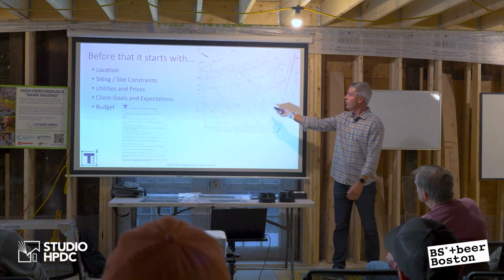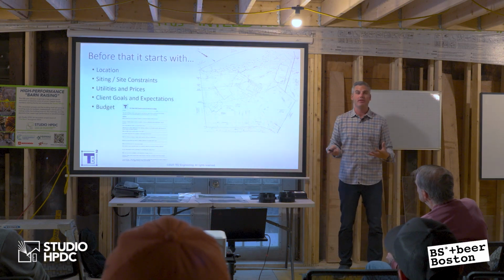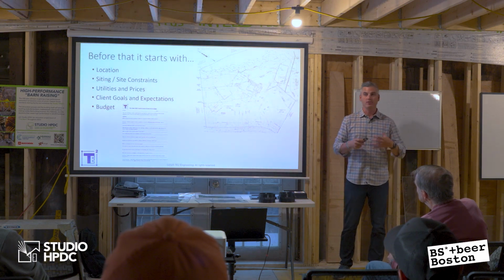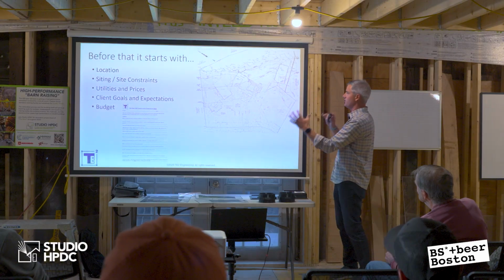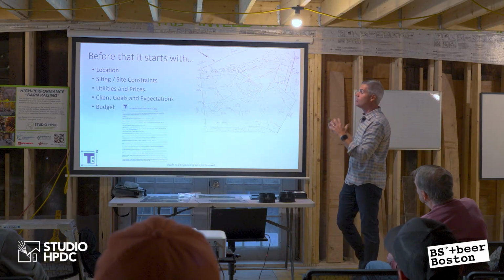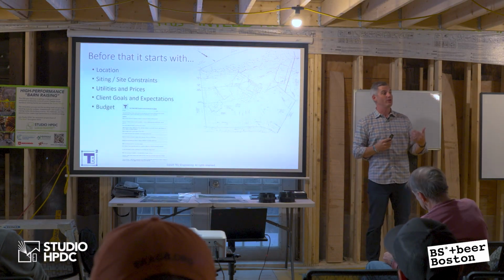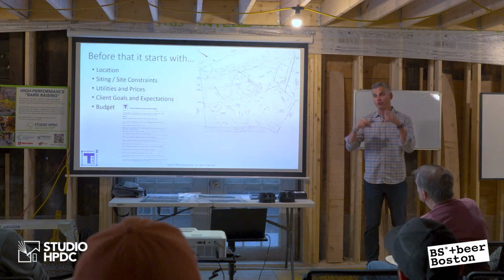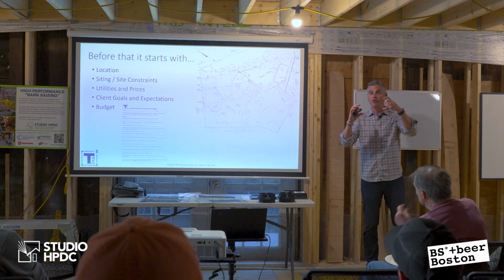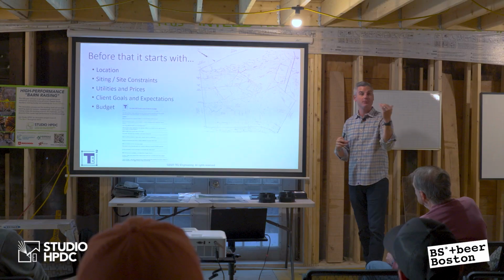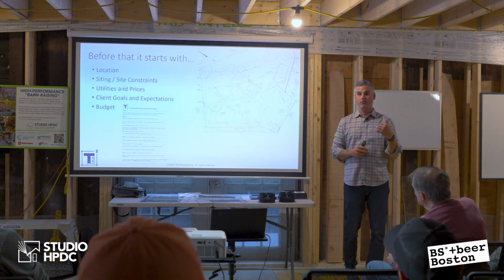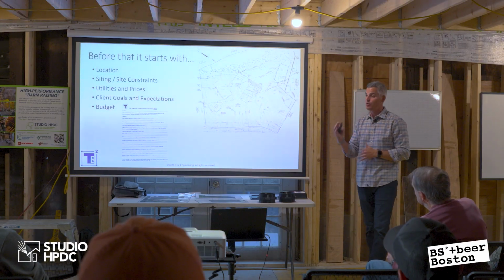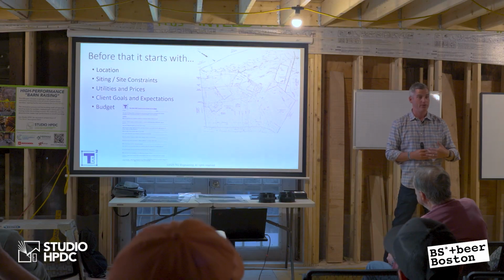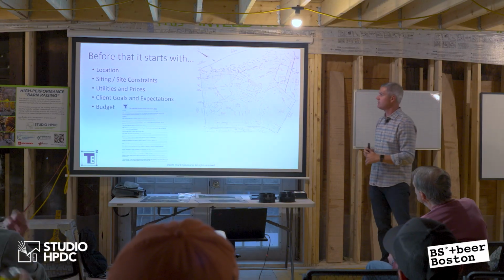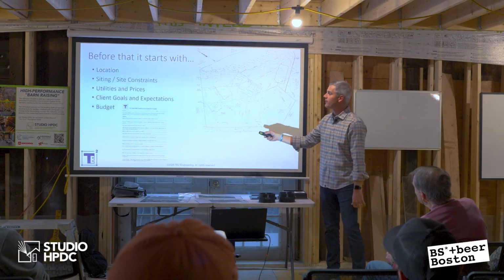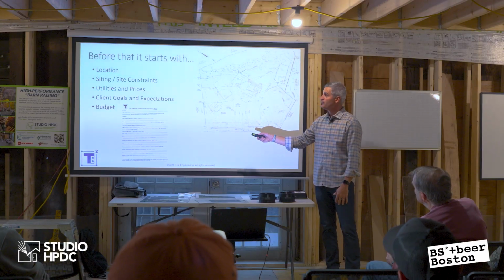Siting and site constraints. What are the siting constraints that we're dealing with? A lot of architects will talk about siting and making sure that it fits well on the site and works well with the landscape, et cetera. We're doing the same thing, but from an energy and comfort perspective. If I can reorient the building, maybe 10 degrees, tilted the other direction, I might actually be able to reduce my cooling loads in that building. I might be able to optimize the building by changing the window style, or window pattern, or the U value, or the solar heat gain coefficient of those windows. So the siting does matter.